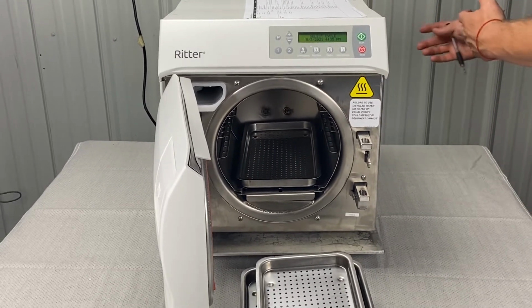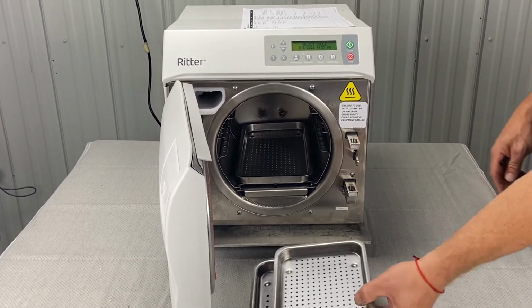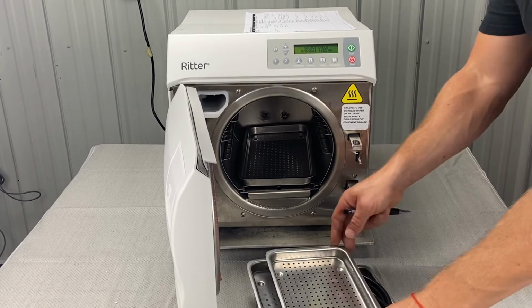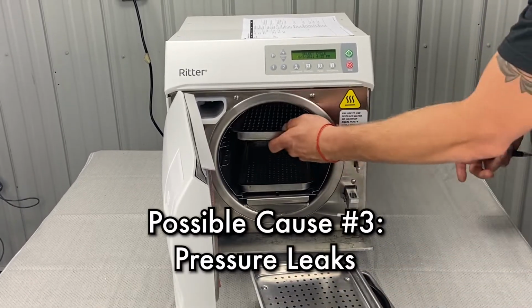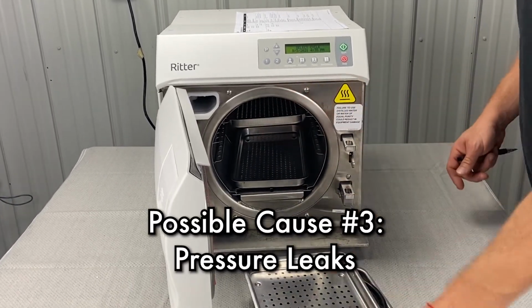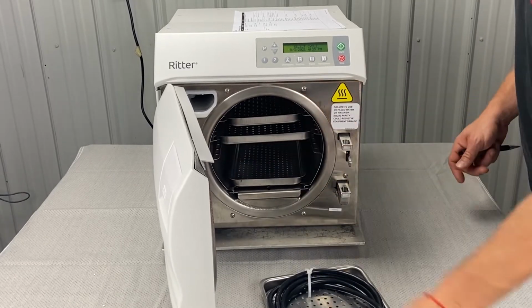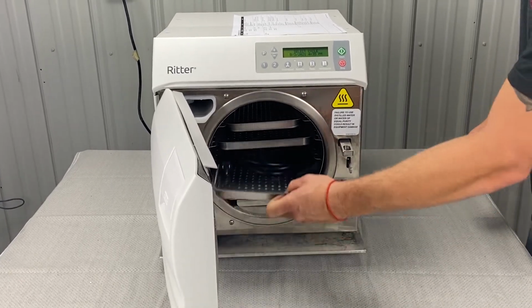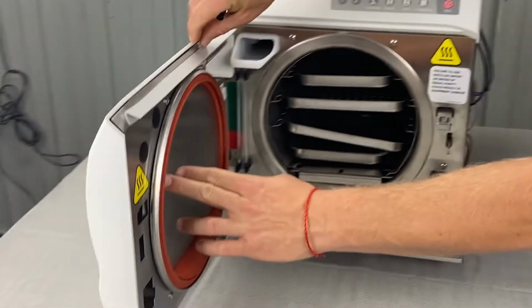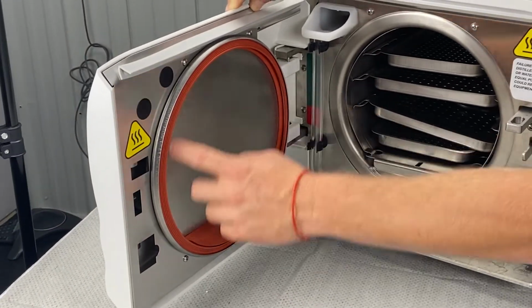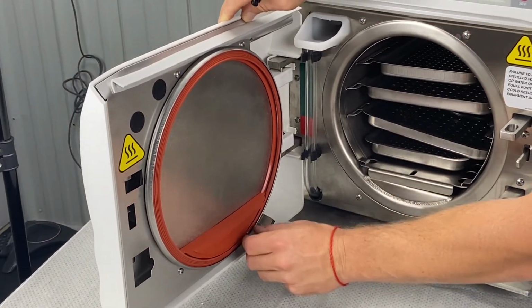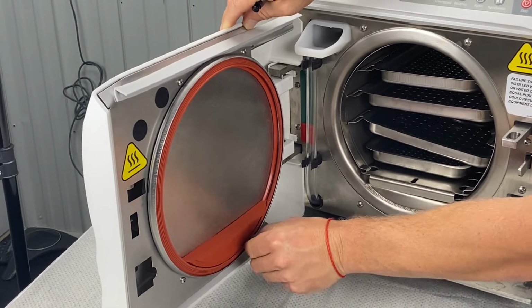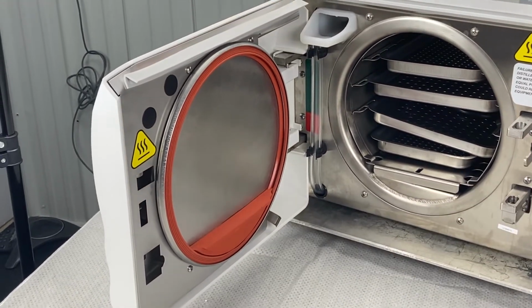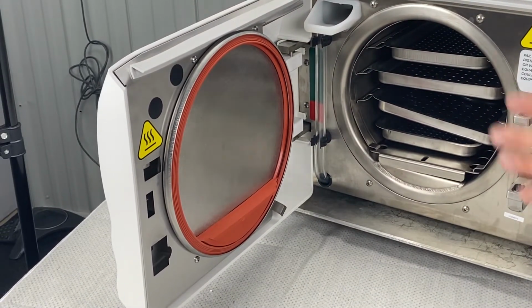and run another cycle. During that cycle, we are going to look for pressure leaks. There are a lot of places that it could have pressure leaks. One is the door gasket. So here's your door gasket. It says that it should be replaced annually, but based on my experience, they should be replaced probably quarterly, or every 2 or 3 months, depending on cycle usage.